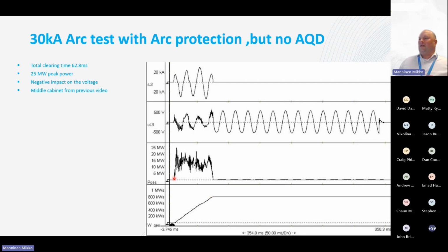So actually the arc flash is already detected here. It can be detected easily in microseconds. That is not very difficult to build. But to react to that, we need to trip the breaker, and that can also be done very quickly. But then the circuit breaker has to open. And when you open the breaker, that is also an arc flash. When you open the breaker, you have another arc flash, which is parallel to this one. So now we have about 60 milliseconds of arc flash until everything is safe.